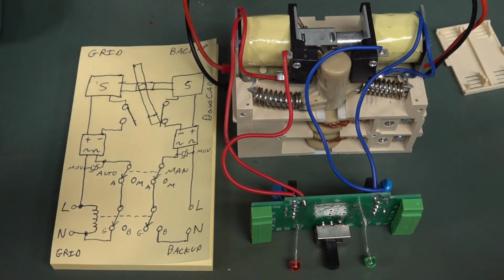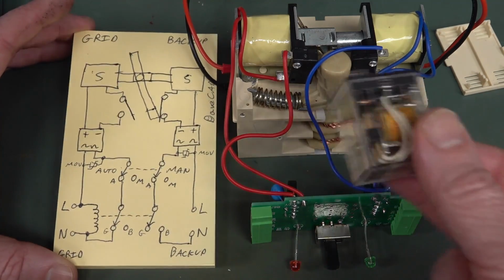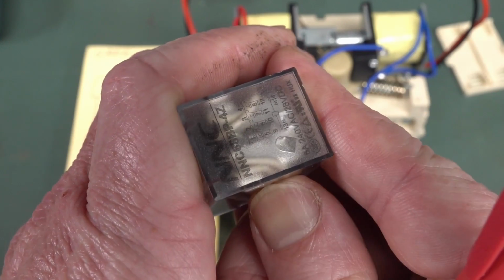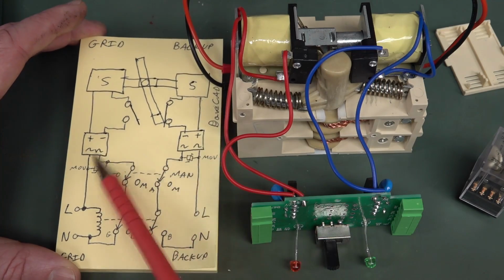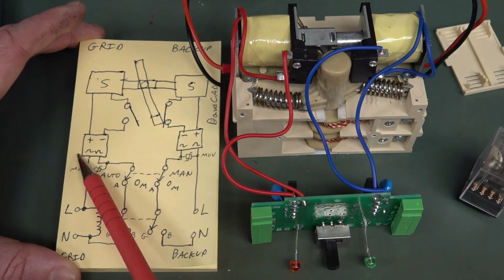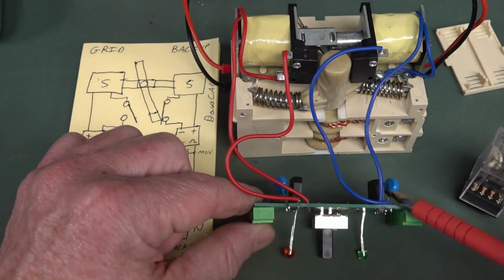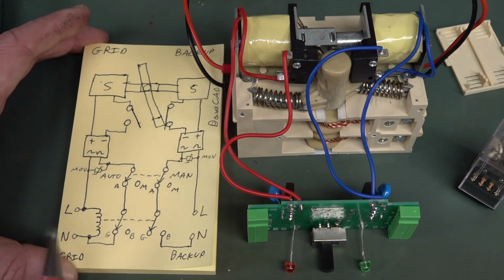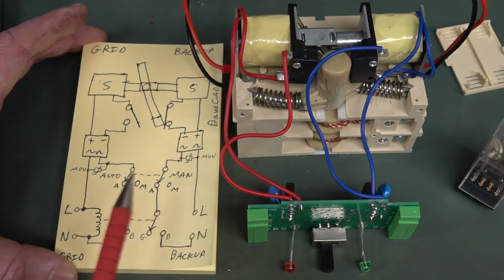I haven't drawn in those extra auxiliary contacts because they have nothing to do with the actual operation of this. Suffice it to say, this is a 4-pole double throw relay in there. And there's 2 MOVs in there across the AC input to the diode bridge. They're the 2 blue MOVs there. They're 681s, which is about 480 volts RMS.